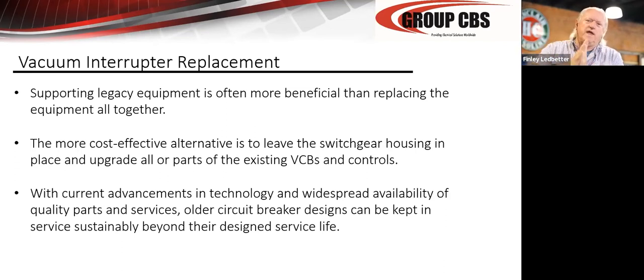You're asking it to hold 1,000 foot-pounds of pressure for 5 years and then operate as if you operated it in a few seconds. That is a lubrication issue. It's a mechanical issue that's hard to overcome. You're asking a breaker to maintain 1,000 foot-pounds of pressure against itself and against the springs, and then react as if it was only a few seconds closed, yet it may have been closed 5 to 10 years. That's the problem. So in order to do that, you have to do all this other work. So replacing the vacuum interrupters at some point is going to be inevitable.